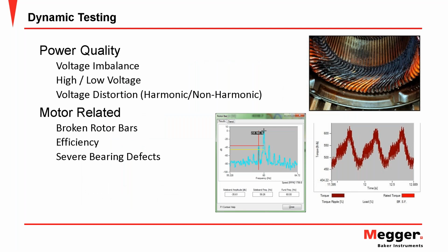And I mentioned before, dynamic testing, again, is going to help us understand the environment. Here you see another motor that's been burned up. It has localized heating. This is a different pattern though, right? It's like a third, or actually in this case, 2/3 of the winding have been overheated. This is caused by a high voltage imbalance, probably caused by a high resistance connection, or in this case, probably a single phasing event. So looking at power quality helps us identify voltage imbalance that can lead to this kind of uneven insulation degradation over time, probably to a lesser degree, but again, our winding is wearing out at different rates. High or low voltage that I mentioned, saturation and higher current. And of course, distortion is an instantaneous voltage imbalance is the best way to describe distortion. And so again, identifying those conditions that maybe we can correct before it has the opportunity to really cause heating damage to our insulation system.